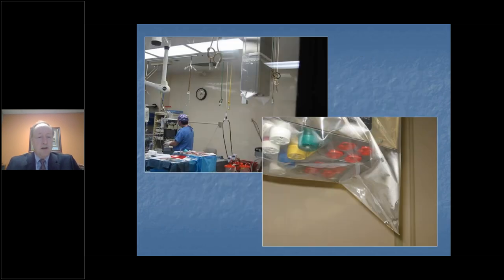Here's an example of an operating room that had some humidity problems. They were dropping the temperature down to probably 60 degree dry bulb temperature, which is where the doctors wanted it. But the problem is they hadn't removed enough moisture from the space, and while all the surfaces were at 60 degrees dry bulb, the humidity level in here was greater than a 60 degree dew point. So you would have a lot of condensate building up on these surfaces and it would drip.